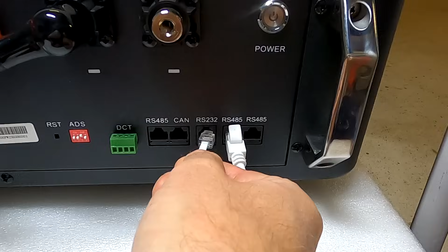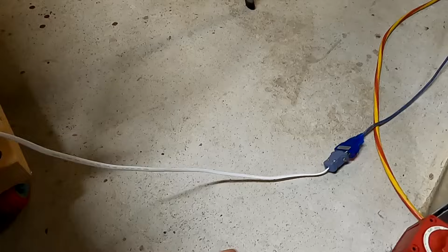All right, then plug in our RS232 cable. This is the cable which is in the box as well, delivered with the battery, goes to your adapter, and then plugs into a USB port on your computer. Okay, we open the BMS Tools software, change our COM port to COM9, in my case RS232, and you can see it has already recognized it is address number 4. If I plug this cable into any of the other batteries now, it will actually update this field here with the correct address of this specific battery.